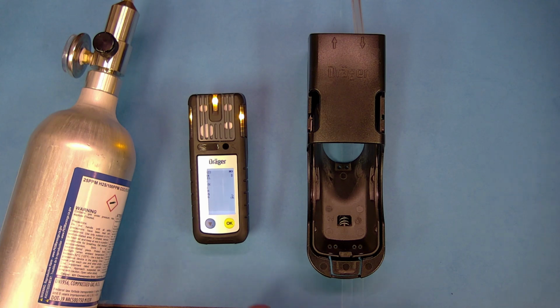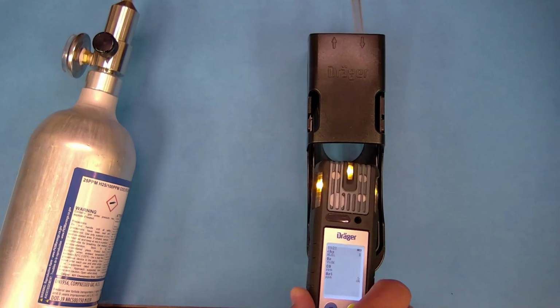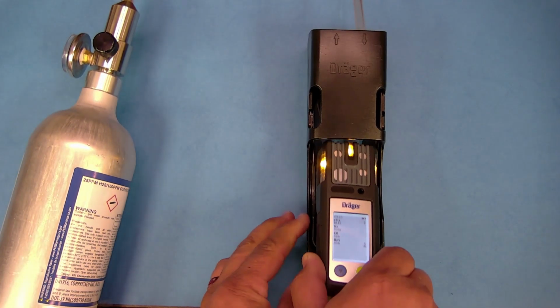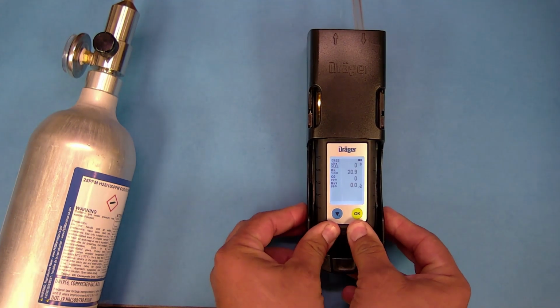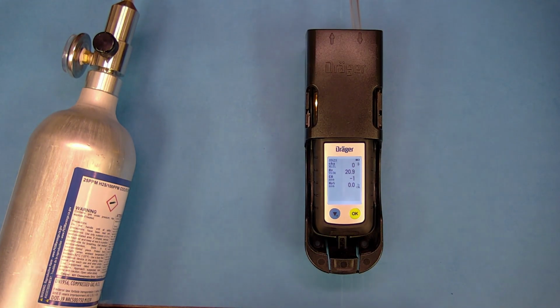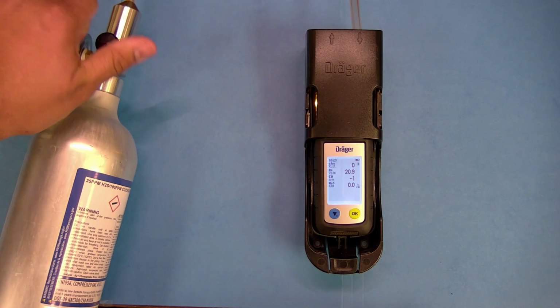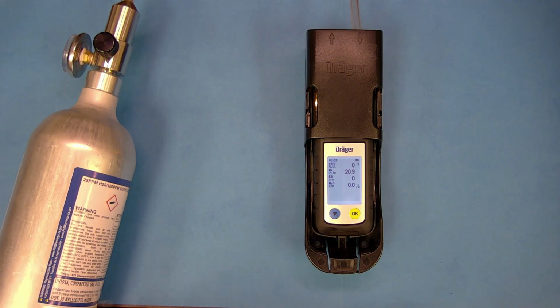From here, you're going to insert the unit into the bump test calibration adapter. And remember to get the firm click with both thumbs, and then you can flow your gas by turning the knob counterclockwise. You will again get OKs on all 4 sensors once they have completed calibration. Once you see all 4 OKs, you can press OK on the monitor and turn off the gas regulator.